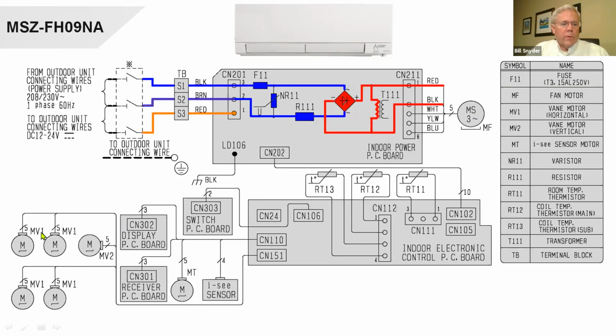Coming down here, we've got this little mark here, which means DC. We've got 1, 2, 3, 4 DC MV1s. Go over here and we see MV1 is a vane motor horizontal, that's for these. And then we have a vane motor vertical here. MV2, also a DC voltage, and it's got 5 wires going to each one of these. Coming in here off of the CN151. Then we have another motor right down here, which is DC. That MT is this motor on the, does it have it on here? Right here, i-see sensor motor, that's right here. So that's driving the i-see sensor back and forth, rotating it, trying to see what's going on in the room. RTs, which are thermistors. Does it tell me that on here?